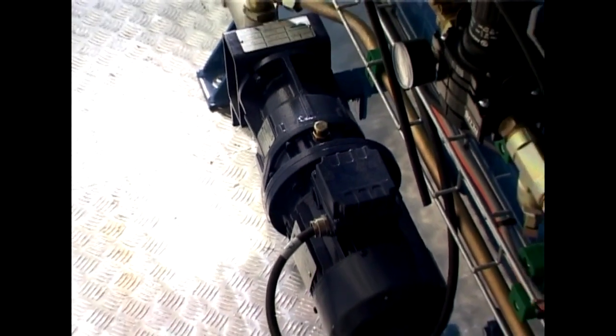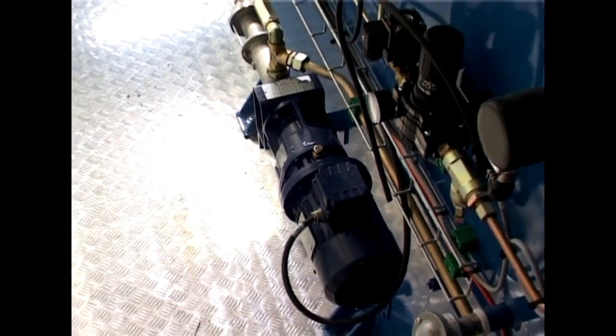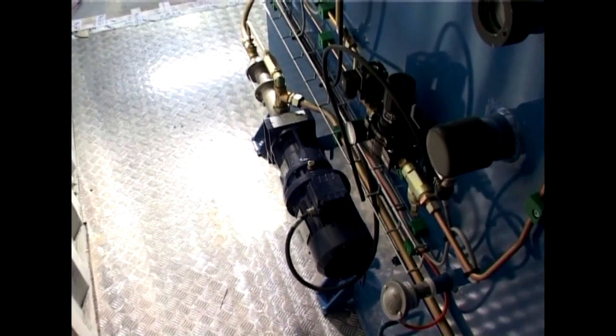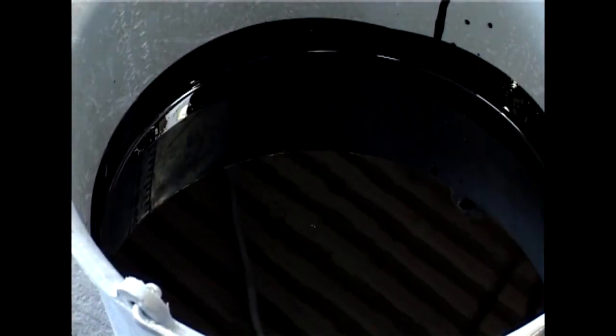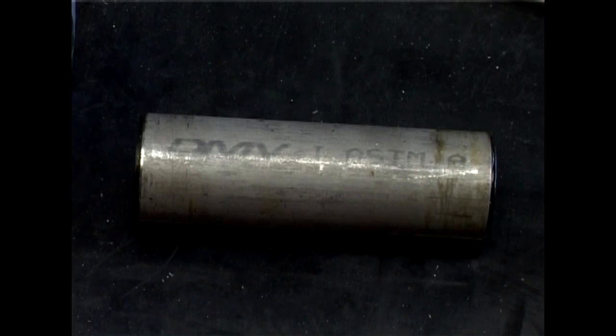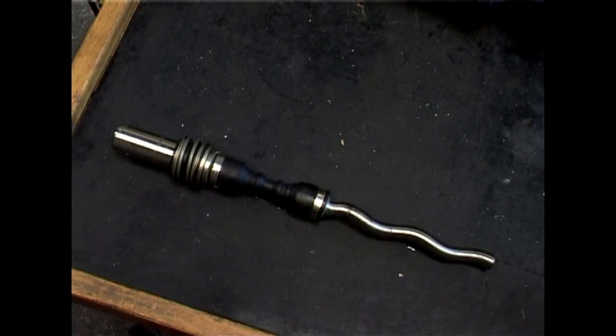If the sludge dosing and oil circulation pumps are not serviced, they will not give pressure, and you are not able to start the sludge oil incineration process. The pumps consist of a stator made out of rubber and a rotor of stainless steel, and they can be serviced by following the procedure shown to you here.